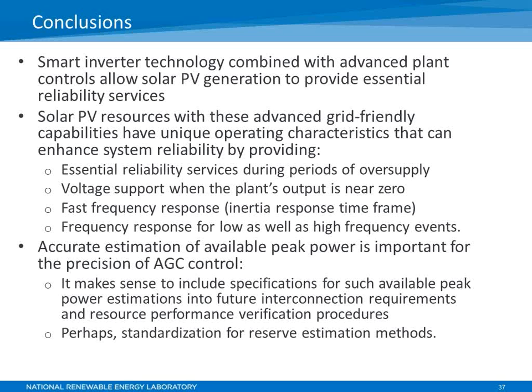One takeaway from this test, and I think it's really important for the whole industry, is that accurate estimation of available peak power is really important for precision AGC control, and also for provision of spinning and non-spinning reserves. Not so many plants have that capability, although the capability already exists commercially. There is no standardized way of evaluating it. There are many variables in a PV plant, such as resource data itself, temperatures of the panels, characteristics of the inverters, and so forth, that need to be taken into account.